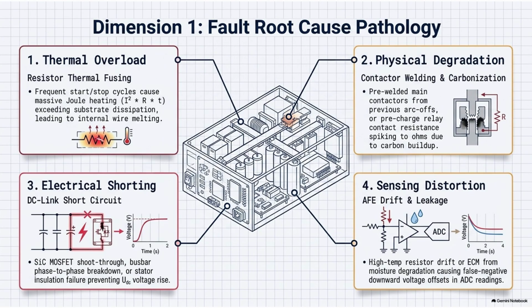But this is where the physics of air come into play. Air is normally a great insulator, but if you try to pull two pieces of metal apart while massive current is flowing through them, the electricity doesn't politely stop. It wants to keep going. The voltage is so high it literally tears the electrons off the air molecules between the separating plates. The air becomes ionized, turning into a highly conductive plasma arc.